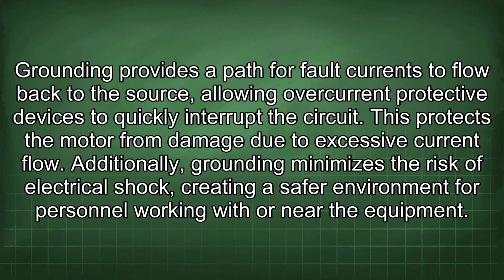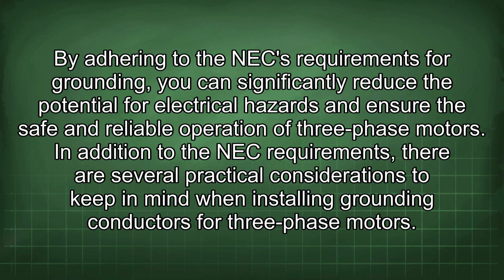Properly grounded motors are less likely to cause electrical hazards or damage to equipment. Grounding provides a path for fault currents to flow back to the source, allowing overcurrent protective devices to quickly interrupt the circuit. This protects the motor from damage due to excessive current flow. Additionally, grounding minimizes the risk of electrical shock, creating a safer environment for personnel working with or near the equipment. By adhering to the NEC requirements for grounding, you can significantly reduce the potential for electrical hazards and ensure the safe and reliable operation of three-phase motors.